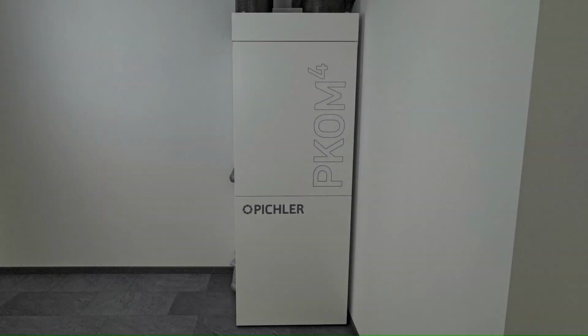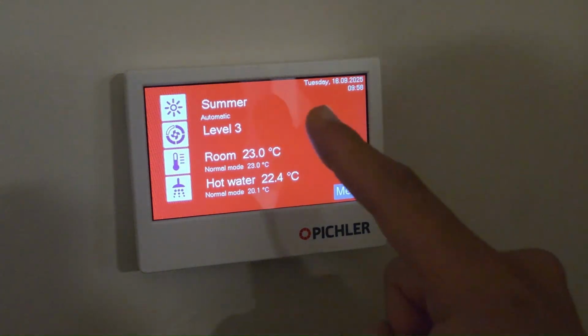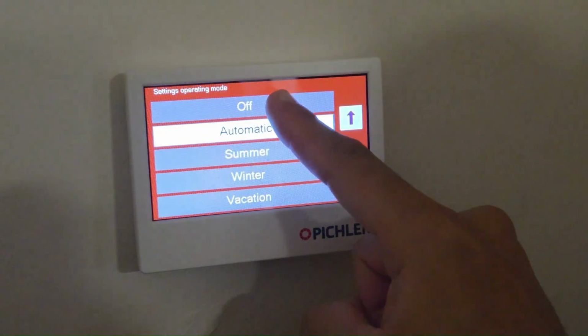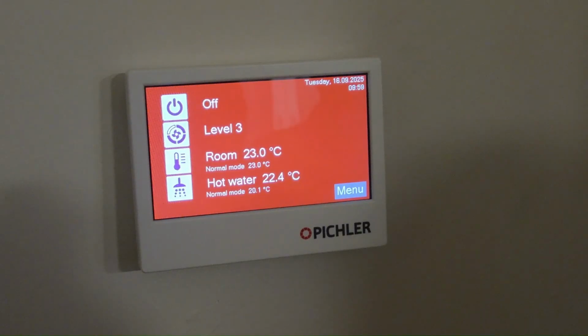Maintenance and cleaning of PICHLER heat pump combi unit. Please observe the following steps and precautions. Switch off the heat pump by setting the operating mode on the control panel to off. Wait for 5 minutes to ensure that the heat pump has come to a complete standstill before proceeding.